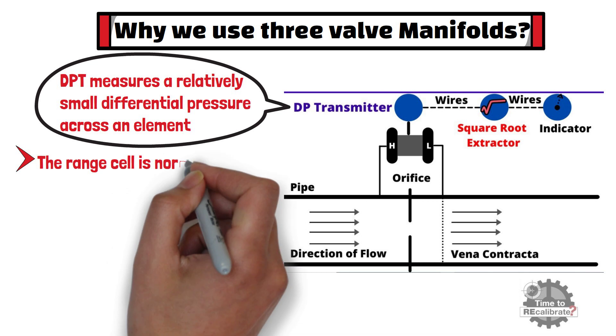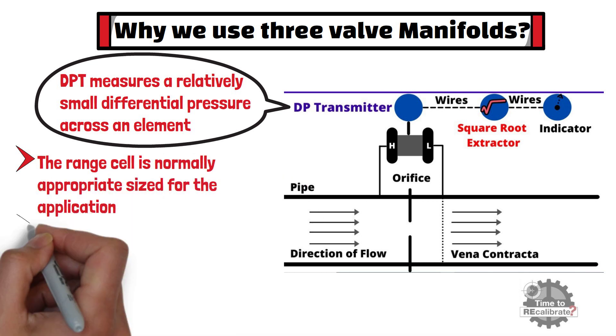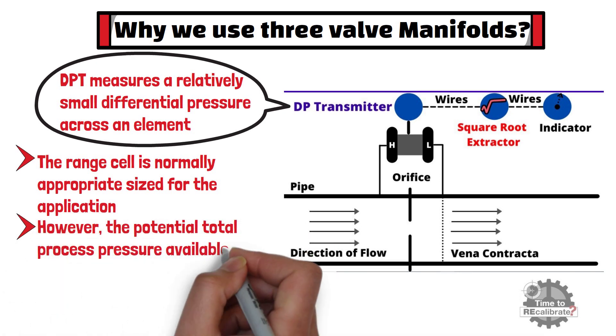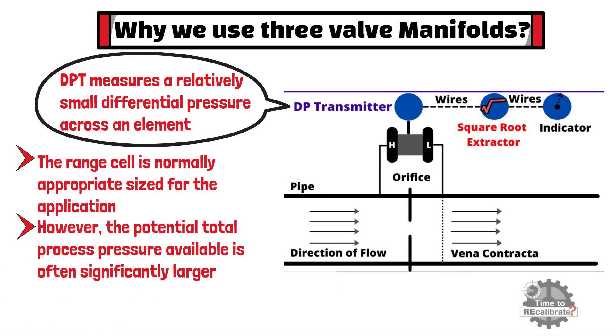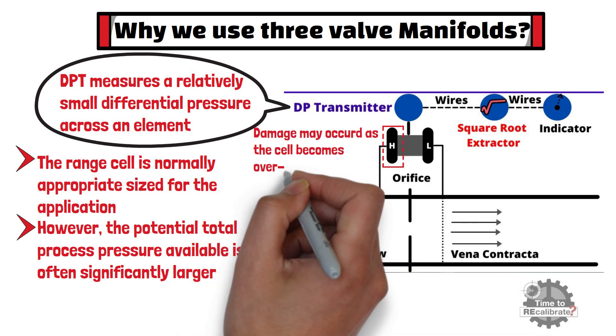The range cell used within the transmitter is normally appropriately sized for the application. However, the potential total process pressure available is often significantly larger, so much so in fact, that if the total pressure were to be applied to one side of the transmitter only, damage may occur as the cell or capsule becomes overranged.